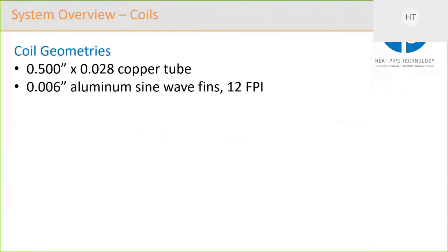So just looking at the coils in general, we're using half-inch pipes, that's smaller than 5/8. We have a 0.028" wall, so it's thicker than our heat pipes. It's a little bit thicker to help with the conditions of the water being pumped through the tube, so to prevent erosion becoming a problem. The sine wave fins are 0.006" thick, and we found the sweet spot is at 12 fins per inch. And also our sweet spot is 6 rows deep.